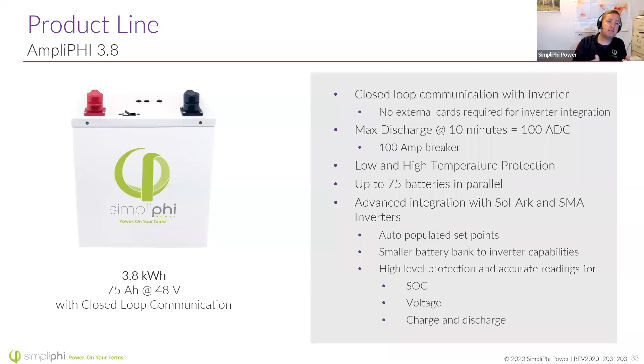SimpliPhis also have a higher max discharge rating, 100 amps at 10 minutes, whereas the standard Phi battery, for reference, is 80 amps at 10 minutes. You are limited to 75 batteries in parallel on the SimpliPhi because of that closed loop communications limitation.